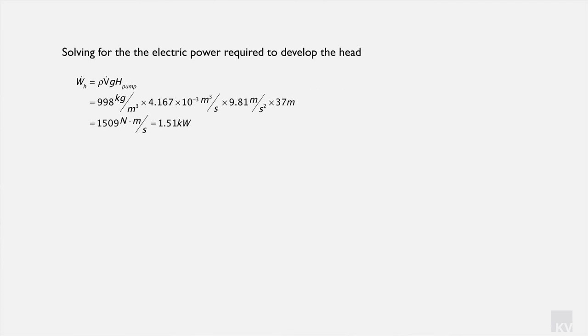Next we solve for the electric power required to develop the head. The rate of work to develop the head equals density × volumetric flow rate × gravity × pump head. Substituting the known density, volumetric flow rate, gravity of 9.81 m/s², and the head of 37 m, we determine that the work required to generate the head is 1.51 kilowatts.